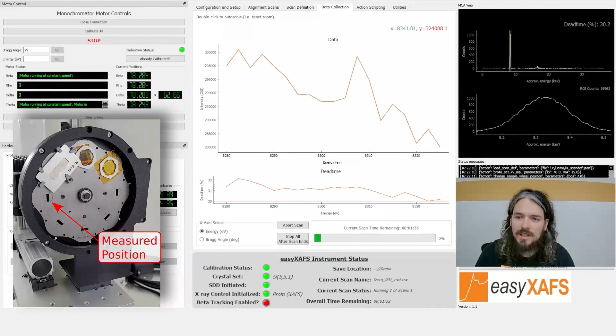As the data continues to come in, we can see it's reached the portion of the scan near the absorption edge where the step size reduces to capture more detail. For the I0 sample, we are measuring with the X-ray beam power at 40 kilovolts and 15 milliamps, so that's half power. This beam power is chosen so that the detector maintains a low dead time to avoid saturation.